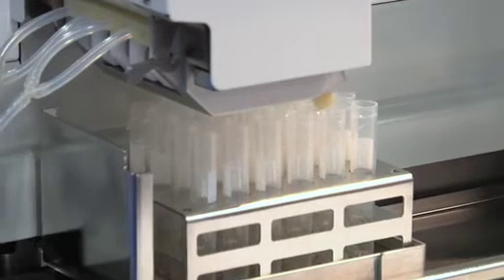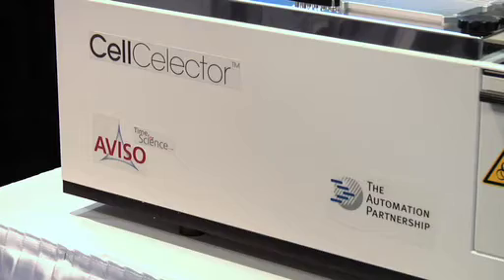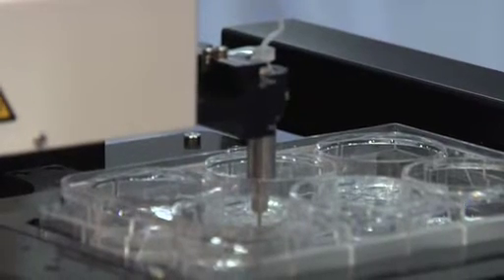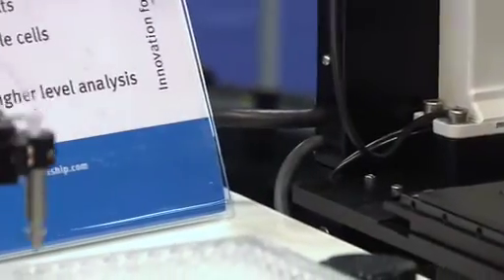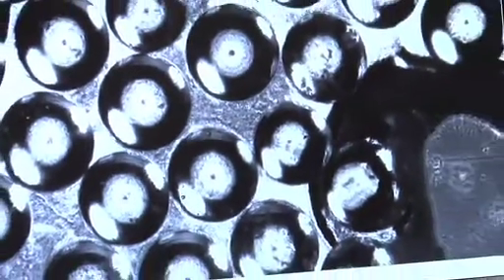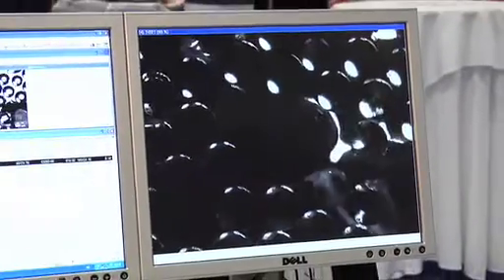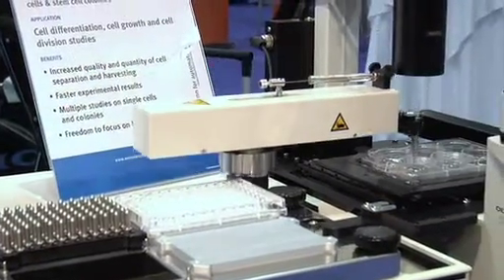Another thing the Automation Partnership is starting to do now is work with other companies and make partners, like AVISO. The other unit we have here on display is the CellCelector. This is from a German company that we've partnered with who has had this unit out for a few years — it is a cell or colony picker. You set your parameters, use the microscope to scan the plate looking for cells that match those parameters, create a pick list, and the unit will go in and actually pick the cells and place them into a plate for your selection.